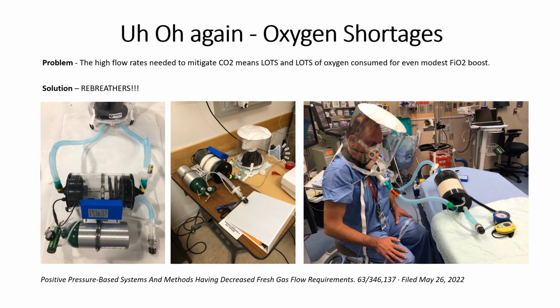So what we were able to set up was taking the scrubber from our commercially available rebreather and doing some creative plumbing with off-the-shelf respiratory components, and ended up with a closed breathing loop that we're able to deliver and adjust that peak pressure from 4 or 5 centimeters of water up to 10 or 12 centimeters of water, and then adjust the fraction of oxygen delivered from low 21 to as high as 90+%, but while only consuming 1 to 2 liters per minute of oxygen, basically just over the metabolic consumption of the patient. So we've advanced this concept with researchers and anesthesiologists at the University of Colorado and University of Washington, and have a pending patent related to positive pressure-based systems and methods having decreased fresh gas flow requirements.